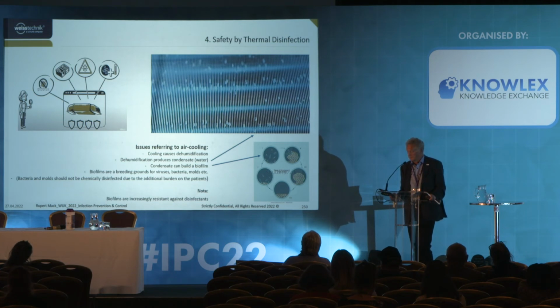They cool, and in the first approach the first task is to cool. Cooling means dehumidification, and dehumidification means water. Water can build a biofilm, especially during shut-off periods, considering there's a long weekend and they shut off the unit because there's no heat inside on Fridays, and after a long weekend they switch it on again on Tuesday. So the biofilm has time to grow.